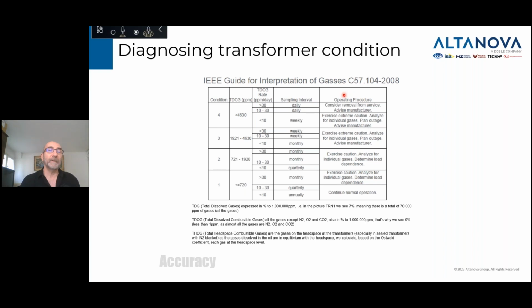Now, all three standards, the IEEE, the Doble, and the IEC, will not give you a diagnostic. They will just tell you if there is potentially a fault developing, what the criticality of that fault could be, and what the next step should be as far as the DGA sampling interval. So if you look at condition 1, if your total dissolved combustible gas is equal to or less than 720 and the rate of increase of your TDCG is less than 10, you continue your normal operation and do your DGA. If it's between 10 and 30, you do quarterly, and if it's higher, you do monthly. And as the gas starts increasing and you go from condition 1 to 2, your sampling has to increase and your operating procedure has to change. But again, that standard is mostly just like an alarm system. It doesn't tell you if you have PD or if you have arcing.